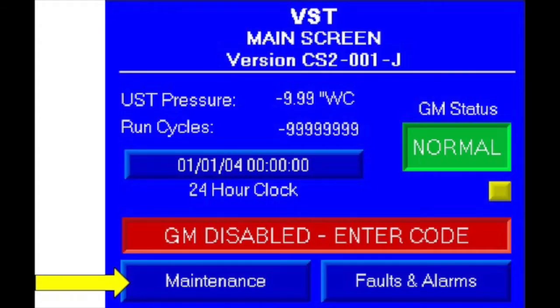When the VST control panel is first powered up for startup, the main screen will show Alarm and will have a message stating that the Green Machine is disabled. The code this message is referring to will be provided upon completion of the Startup Contractor Checkout Form, also known as Appendix B. The Startup and Appendix B sections of this manual are very closely linked, so both sections will be covered in this video.